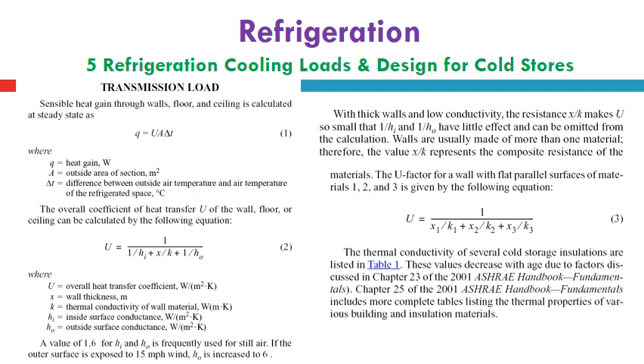such this wall can be considered the side walls facing north or south or east or west, or the ceiling or the floor. In meter, the thickness will be taken in meter using SI units. K is the thermal conductivity of this wall material in watt per meter Kelvin. HI is the inside surface conductance or the convective heat transfer coefficient for inside surface of this wall under calculation in watt per square meter Kelvin. HO is the outside surface conductance or convective heat transfer coefficient of the external surface of this wall from outside, also in watt per meter square Kelvin. A value of 1.6 for HI and HO is frequently used for still air.